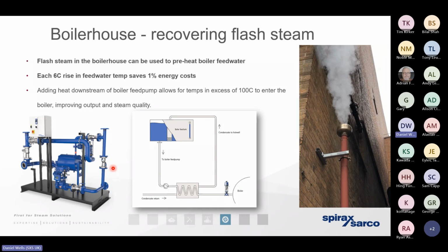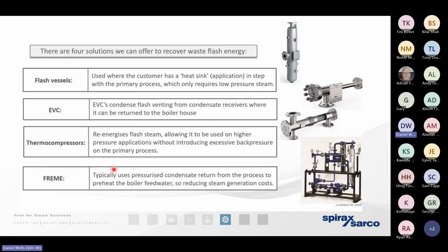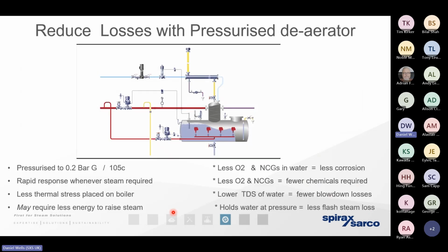So if we know the mass of condensate, and if we know the extent to which it's depressurizing, for example, 100 kilograms depressurizing from 7-bar gauge to atmospheric, we then know the mass of condensate that's going to boil off. In other words, the mass or the volume of steam that's produced, but we also know the energy content of that steam. And once we understand that, we can then look at various solutions where we can allow that expansion to take place, but we can capture that energy and potentially divert it back to another process, another heat sink.